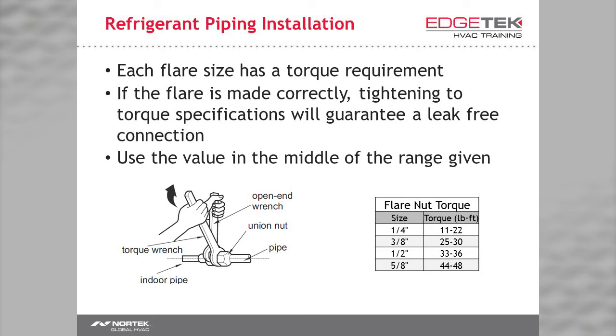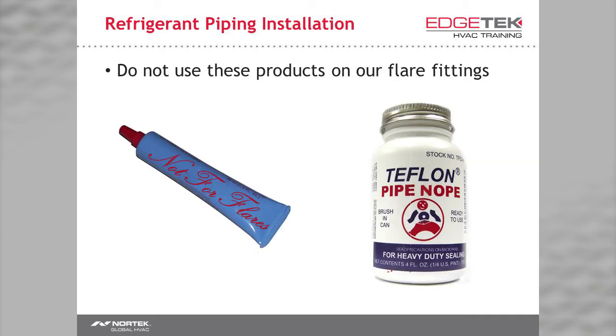Always use a backup wrench like an adjustable wrench. Never use slip joint pliers, as it will strip the brass fitting. I had to change these a little to stay out of trouble, but everyone knows what they are. Do not use any type of joint compound or sealing tape on our flares. If it is leaking, cut it off and try again. I have found small blue balls inside of returned units in the past. Don't let that be you.